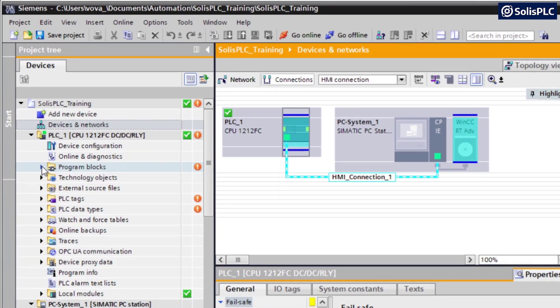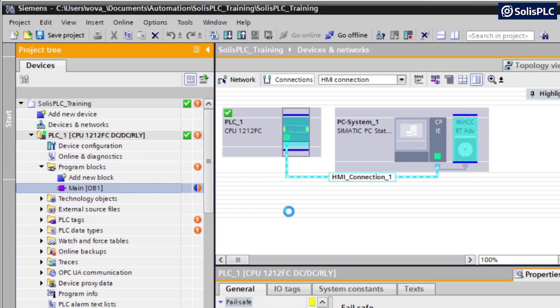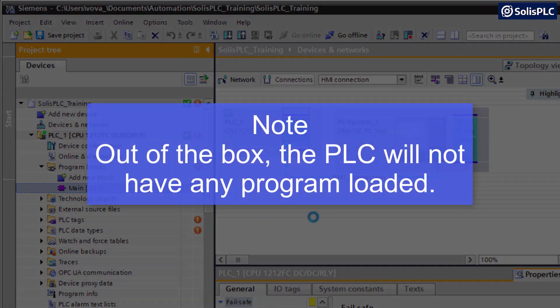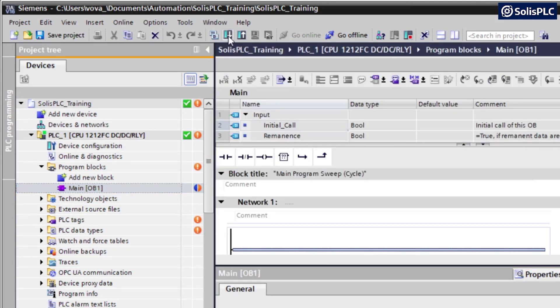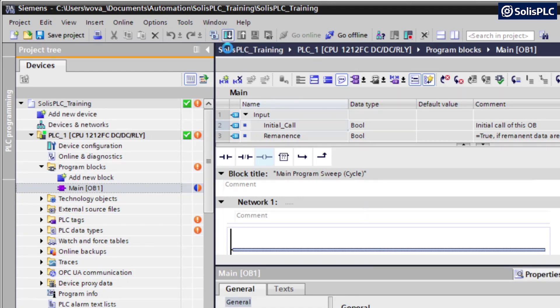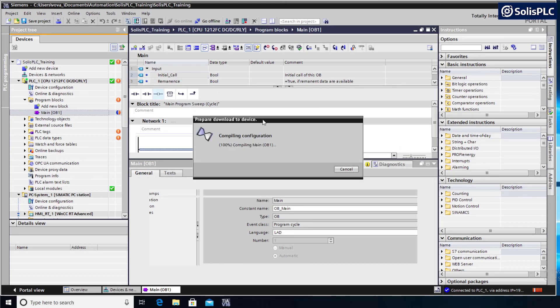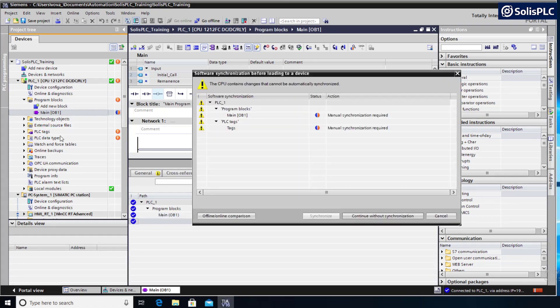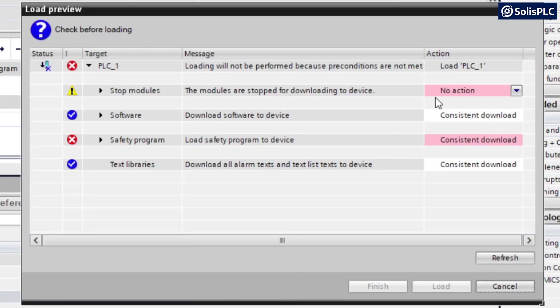The warnings are going to happen due to the fact that there are differences between the online PLC and the program that we have in our project. So in order to download the program, we need to resolve these issues. We're going to navigate to Program Blocks, expand the main OB1. In my case, since we haven't written any program, there should be a single rung. The warning is because it is different on the online PLC. Once we are in this program, we're going to be able to either download to the PLC or upload in certain instances. Here I'm going to proceed with a Download to Device. We should be given a warning that we're going to overwrite the configuration of the PLC. We can continue without synchronization if we want to overwrite the program.